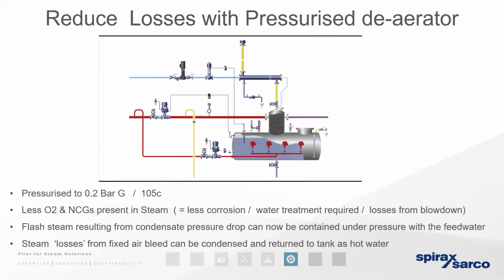So that means not only have we got a cost saving by reducing those chemicals, it means, point six, we need to perform far, far less blowdown of the boiler. If we're adding fewer chemicals into the boiler itself or into the deaerator, it means we need to purge less hot water away from the boiler to waste. Huge cost saving.